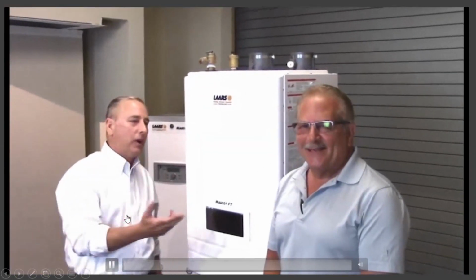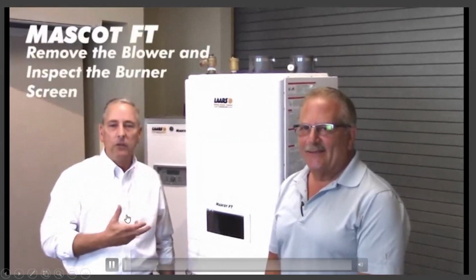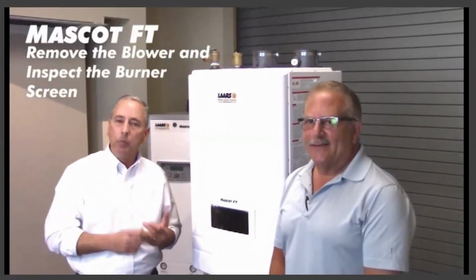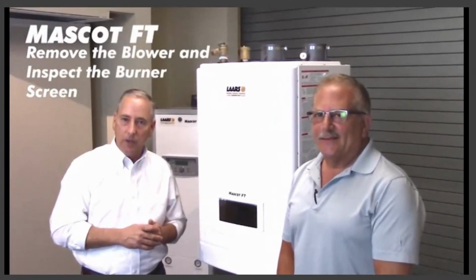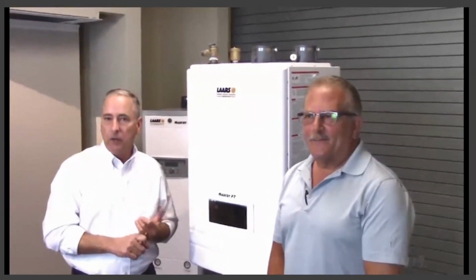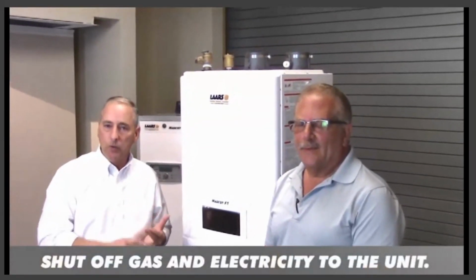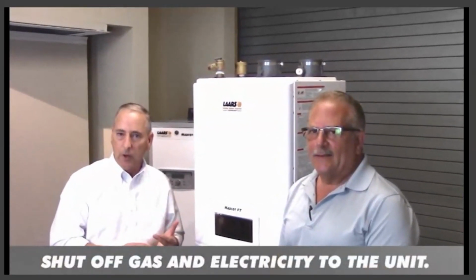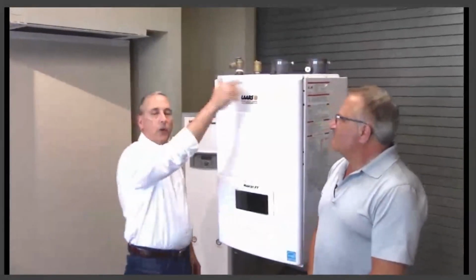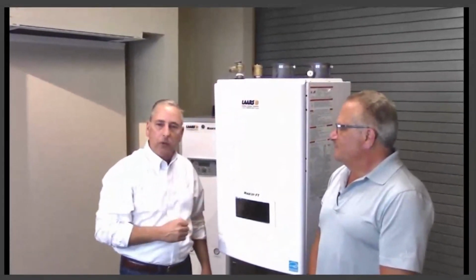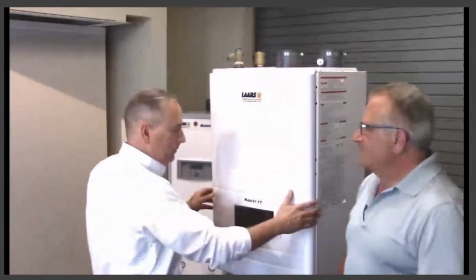Hi, my name is Steve Moruzzi. We're here with Ken Resnick. This video is intended to show how to remove the blower and burner on the Mascot FT. You will need to isolate the gas, shut off gas to the boiler, and remove electricity for this repair. We've already removed the 2 Phillips head screws on the top, 2 Phillips head screws on the bottom. We'll remove the cover.